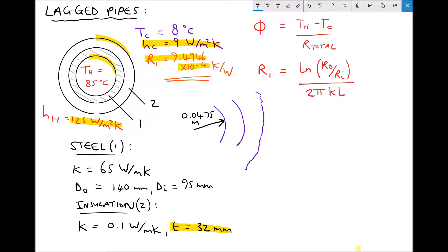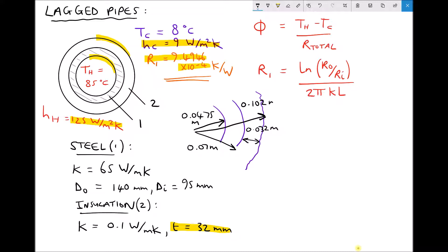The outside diameter of the pipe was 140 millimetres, so the outside radius must be 70 millimetres, or 0.07 metres. We have a lagging thickness of 32 millimetres, which is 0.032 metres. Therefore the radius from the centre of the pipe to the outside of the lagging must be 0.07 plus 0.032, which is 0.102 metres.